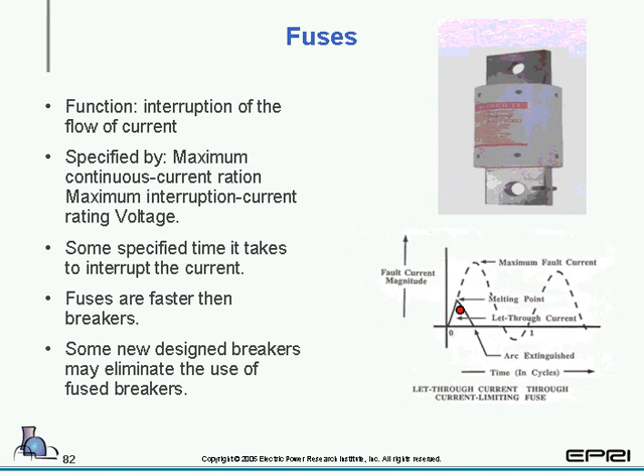If you take a look at a fuse, you'll see that the fuse is set and it's only a partial cycle. And most of them contain some sort of sandy type silicon that when the material is heated will turn to a form of glass, which prevents the flow of current and also prevents the voltage from exceeding a specified amount and jumping across the phases of the fuse.